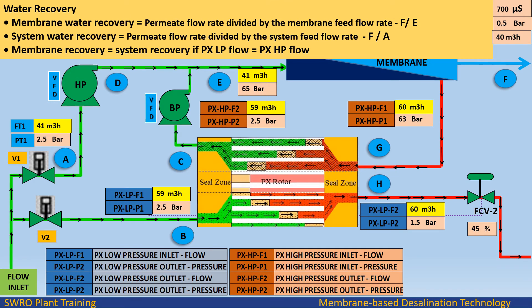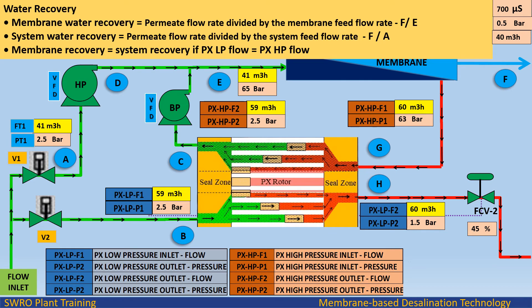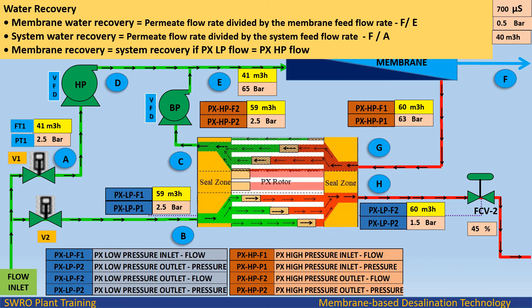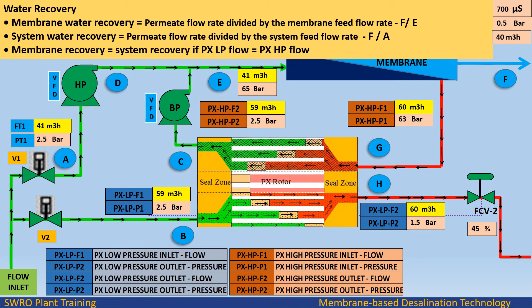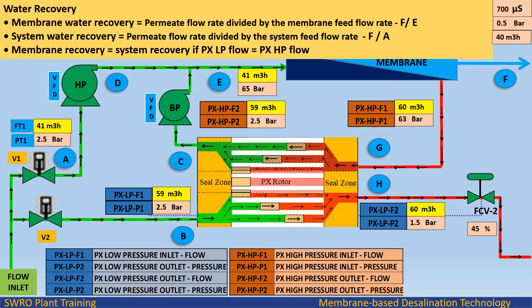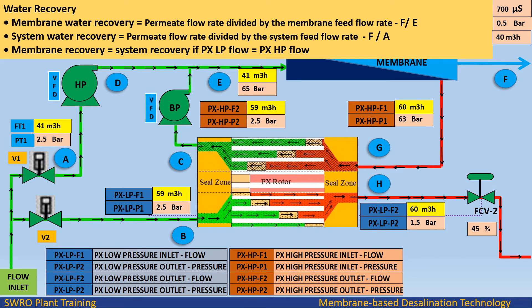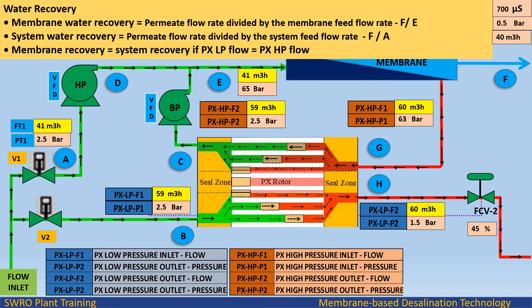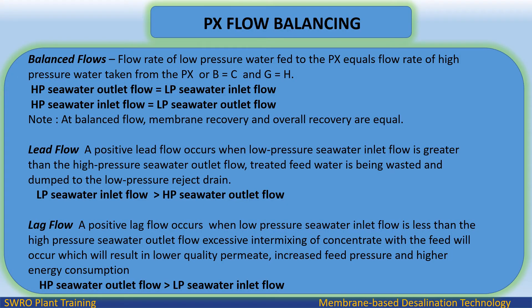Water recovery: membrane water recovery equals permeate flow rate divided by membrane feed flow rate (F/E). Membrane water recovery equals system recovery when PX LP flow equals PX HP flow. PX flow balancing — balanced flows: the flow rate of low-pressure water fed to the PX equals the flow rate of high-pressure water taken from the PX, where B equals C and G equals H. HP concentrate water outlet flow equals LP concentrate water inlet flow, and at balanced flow, membrane recovery and overall recovery are equal.